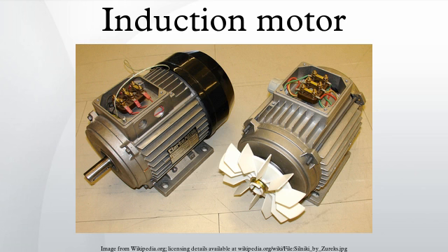In certain smaller single-phase motors, starting is done by means of a shaded pole with a copper wire turn around part of the pole. The current induced in this turn lags behind the supply current, creating a delayed magnetic field around the shaded part of the pole face. This imparts sufficient rotational field energy to start the motor. These motors are typically used in applications such as desk fans and record players, as the required starting torque is low, and the low efficiency is tolerable relative to the reduced cost of the motor and starting method compared to other AC motor designs.